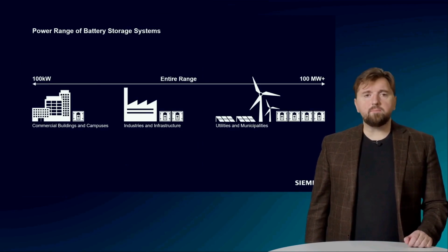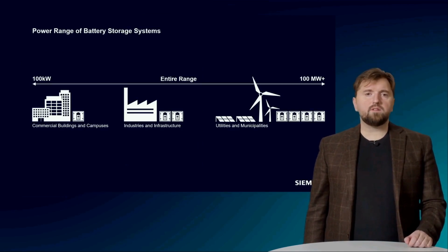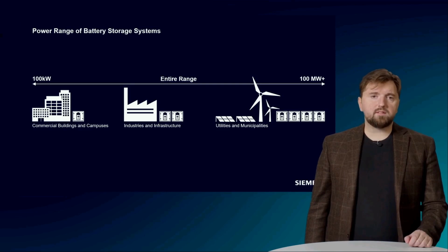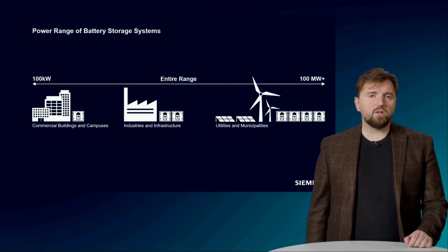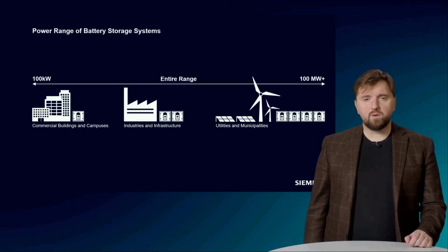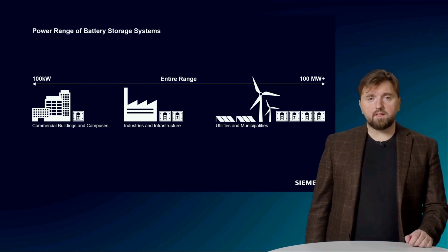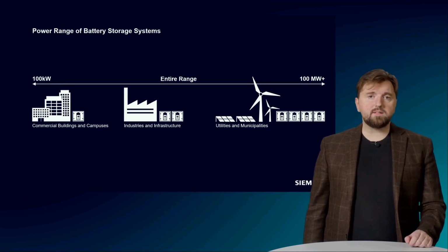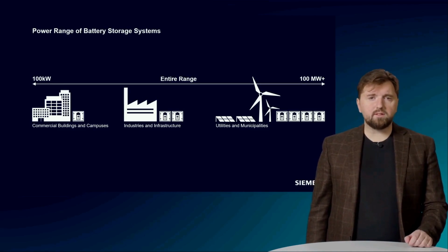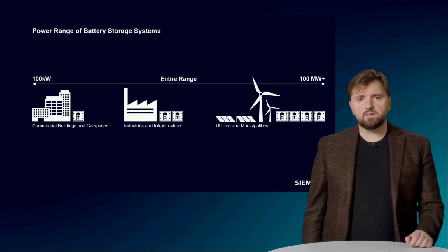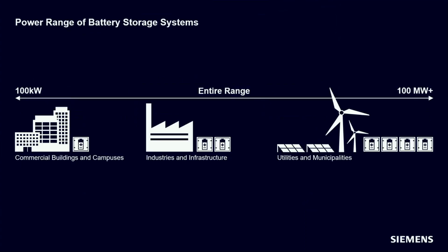When considering the power ranges of BESS, depending on the segment, we observe sizes ranging from 100 kilowatts to 100-plus megawatt. At the utility scale, relative to the system size, we can say that the batteries of several dozens of megawatts are already considered as significant installations. In a large interconnected system, 100-plus megawatt would be seen as a big battery. Let's look at some of the significant BESS projects in service today.